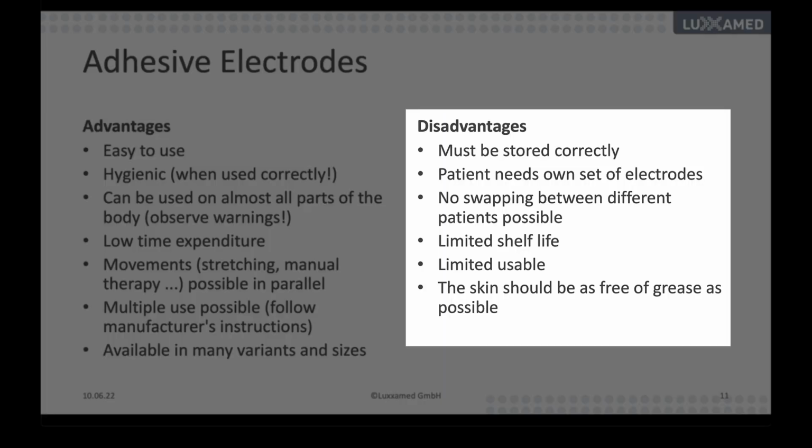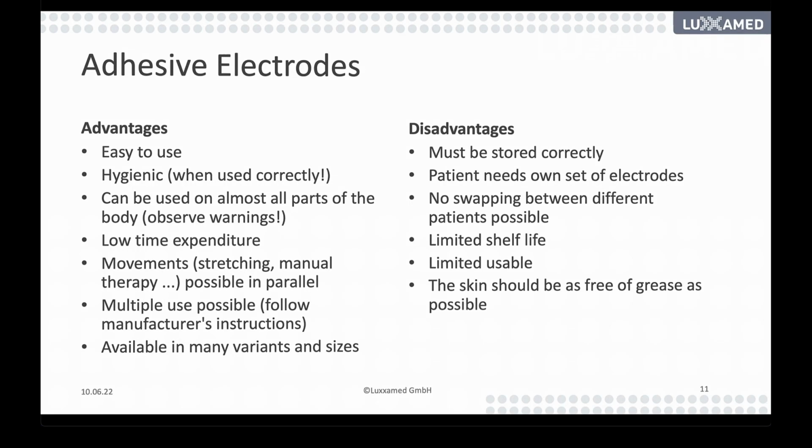In the disadvantages, okay, you have to store them correctly. The patient needs their own set of electrodes because it's not allowed to swap between different patients. You have limited shelf life on the electrodes. After the end of shelf life, it's not allowed to use them anymore. They are also limited in use, of course. If they dry out through use, or if the patient's skin has grease on it, something like this, then they may be very limited in use.